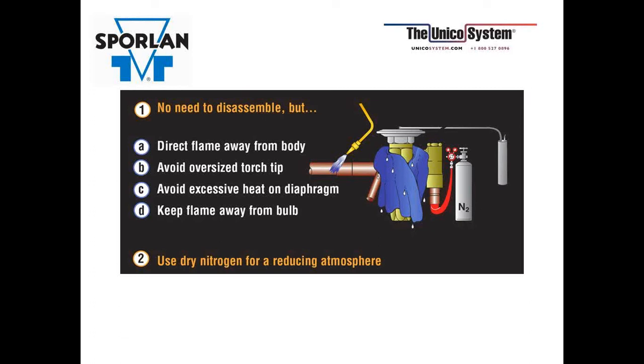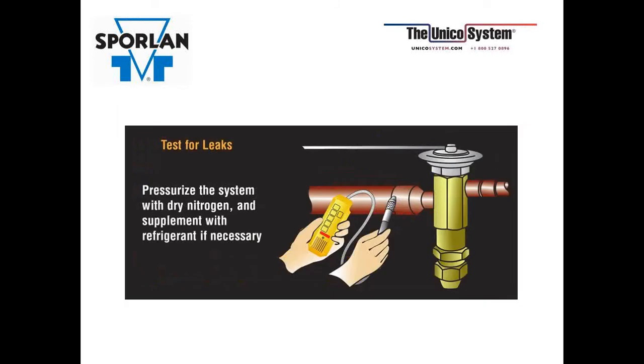If you happen to have the July issue of RSES Journal, there's an interesting article by Bob Henson of Harris Products Group on the importance of using nitrogen while brazing to prevent the formation of oxides during installation. It has some good pictures of some pipes where they used nitrogen and where they didn't, in the formation of the oxide scale. And today with POE oil, that cleaning action of POE oil will clean those oxide scale from the tubing wall, and it's going to deposit in the strainers, the ports, or any other small passageways for pilot-operated components. And then finally, you want to test for leaks.